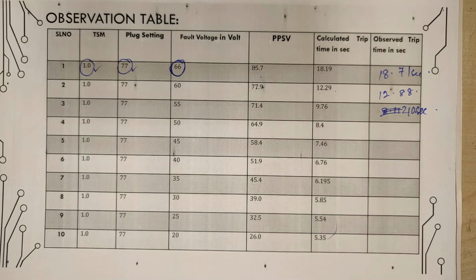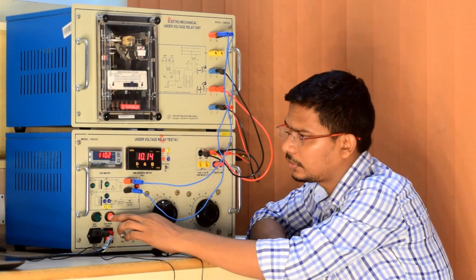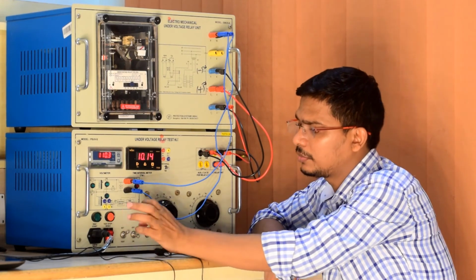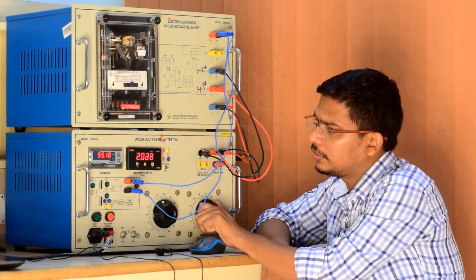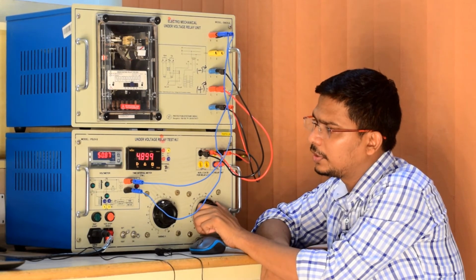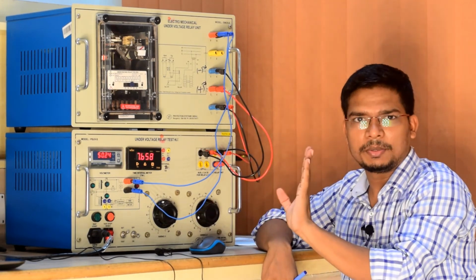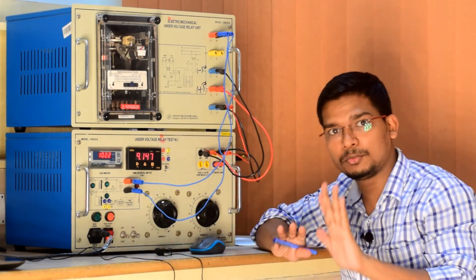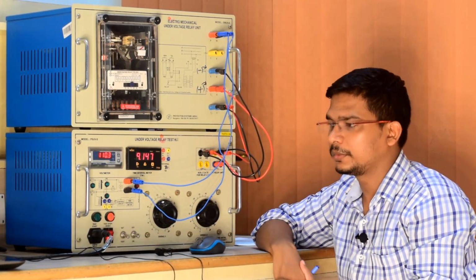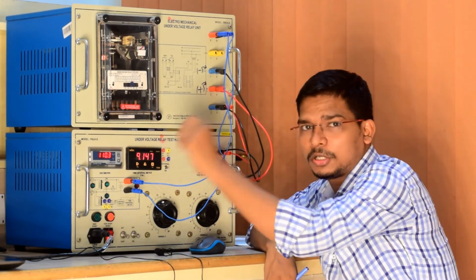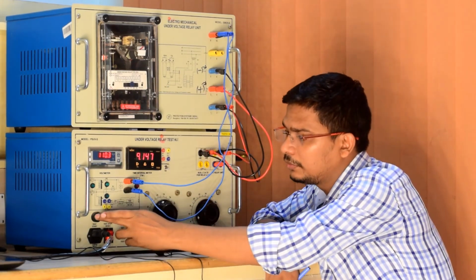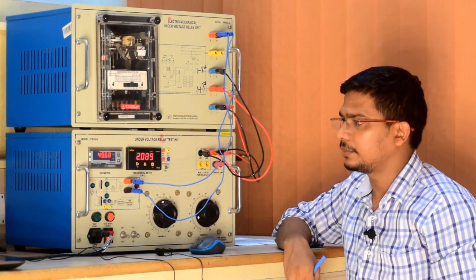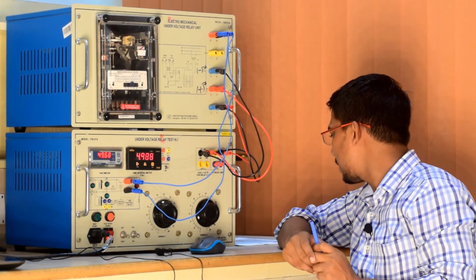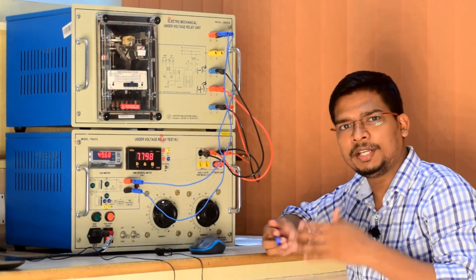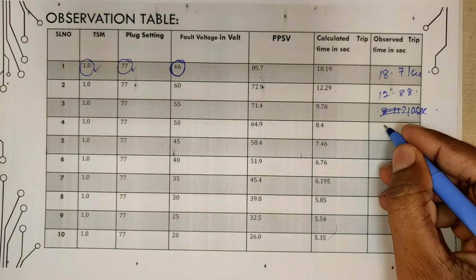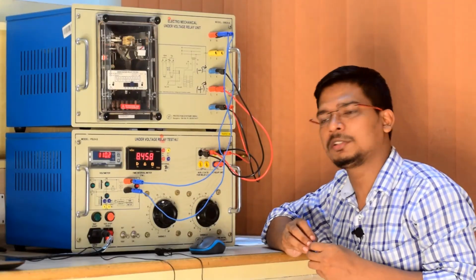So we have applied 55 volt. Now I will apply 50 volt. Turn off, this should be test mode, set, and we have to apply 50 volt. Turn off, test, and you wait. This is the procedure: wait a little bit, so that the relay comes to its normal operating mode. Then we test and start it again. For 50 volt, how much is the expectation? 8.4. It should come near that, as we have already calculated the time. If it is deviating, that means something is wrong.